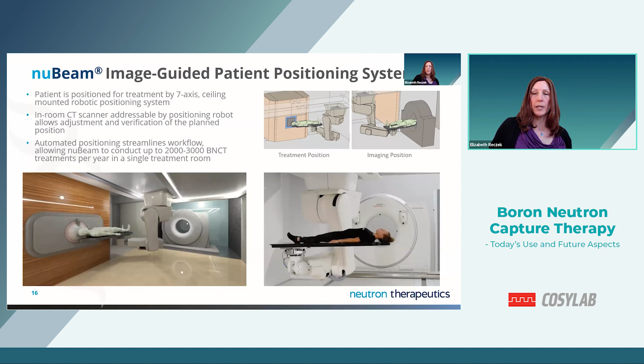Treatment workflow is a key component of the nuBeam system, allowing for potential throughput of more than 2,000 treatments per year at peak utilization. To achieve this, nuBeam utilizes a 7-axis ceiling-mounted robotic positioning system for both imaging and patient positioning to ensure fast and accurate treatments. The images in the upper right-hand corner show the patient in the treatment position and imaging position respectively. The image on the bottom left shows a rendering of the treatment suite in Helsinki, and the image on the bottom right shows the actual installed solution. Automated imaging and patient positioning allows for more accurate treatments without the need for tedious manual measurement and positioning solutions.